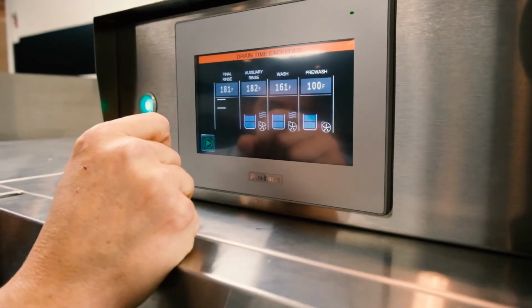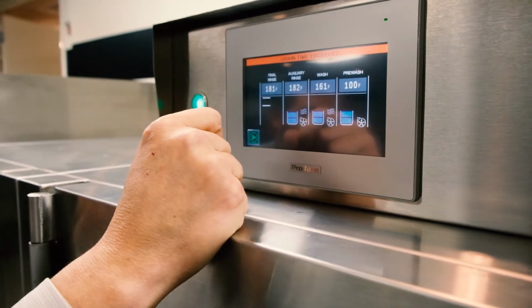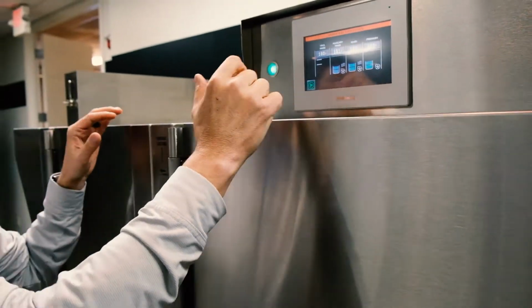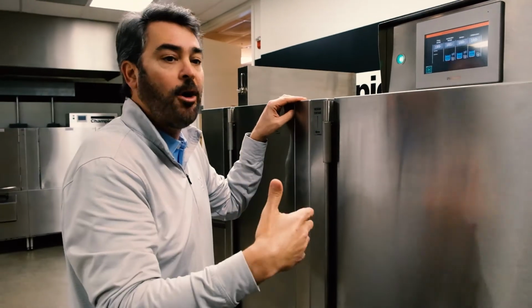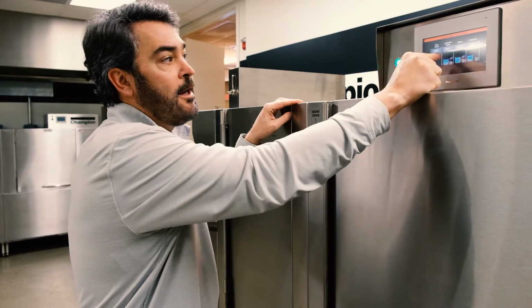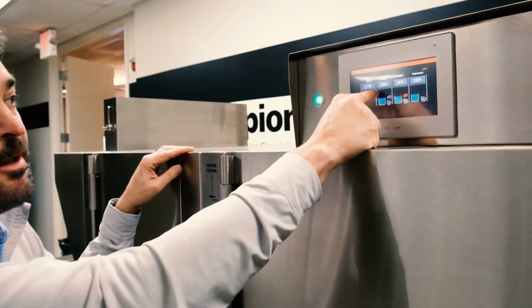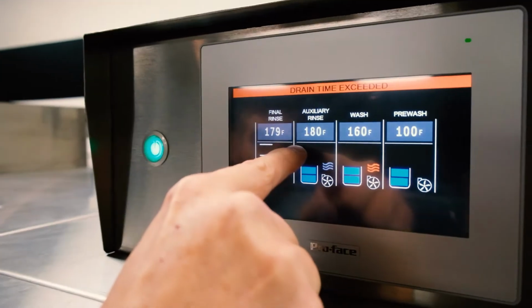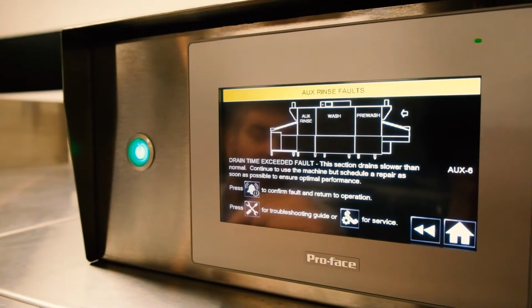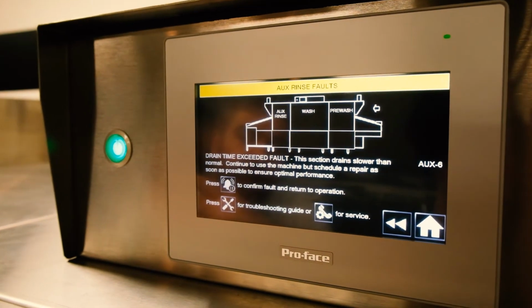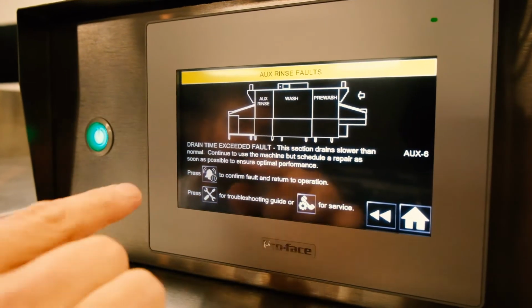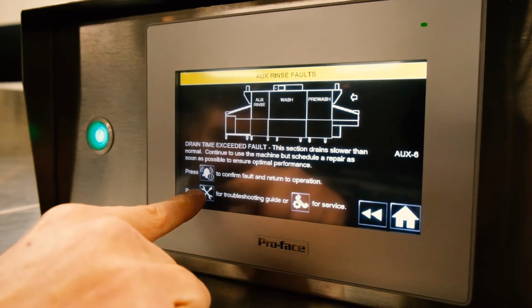If it's green, that means everything is good. If it's yellow, that's usually just a notification saying it's time to change the water or time to D-lime it. But here you can press the exclamation point, and it will tell you: drain time has exceeded fault. This is what you need to do, and you can go in here for a troubleshooting guide.